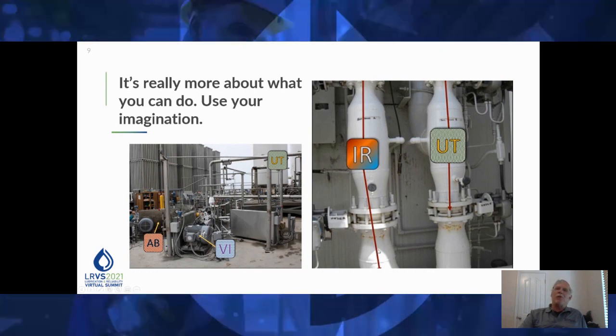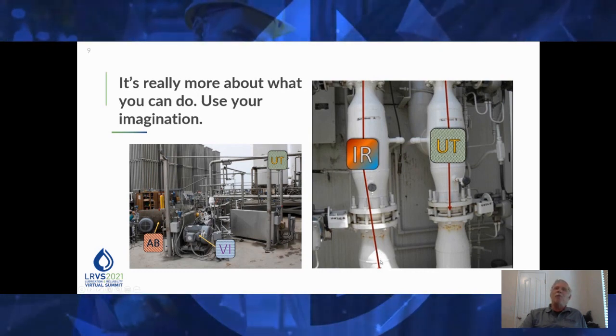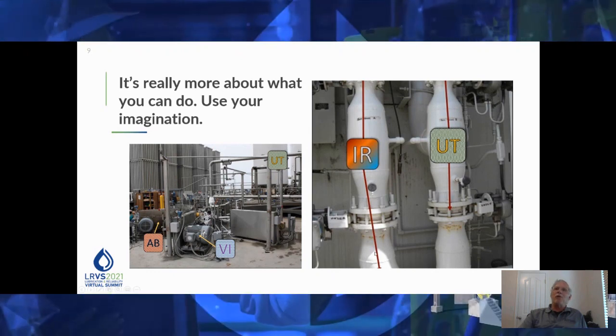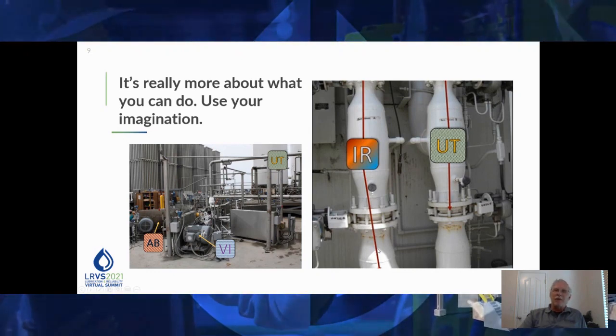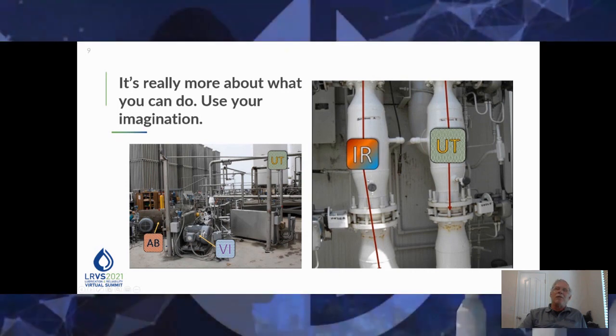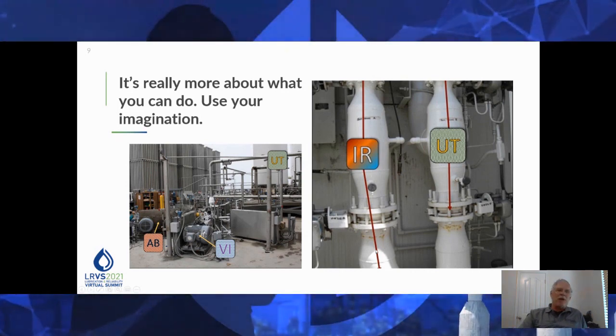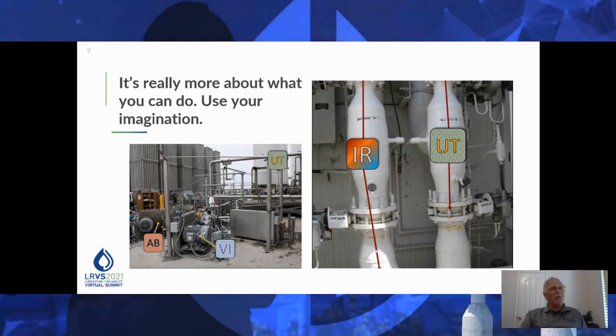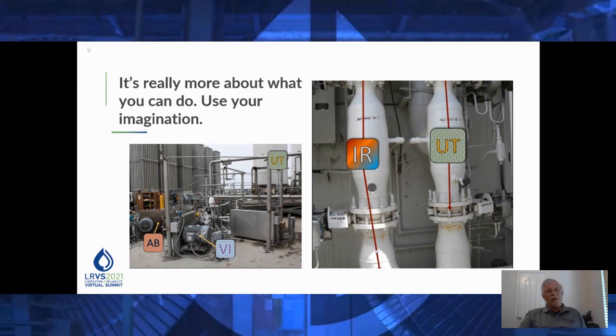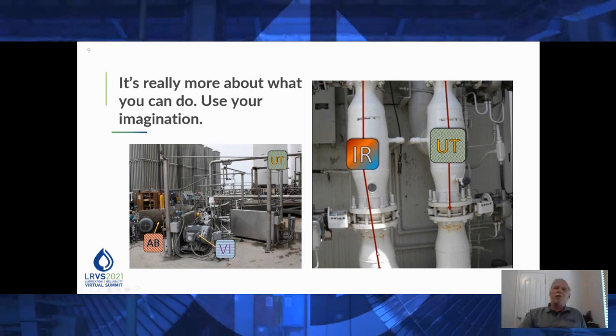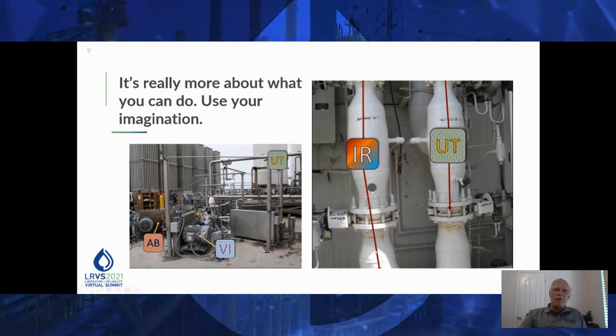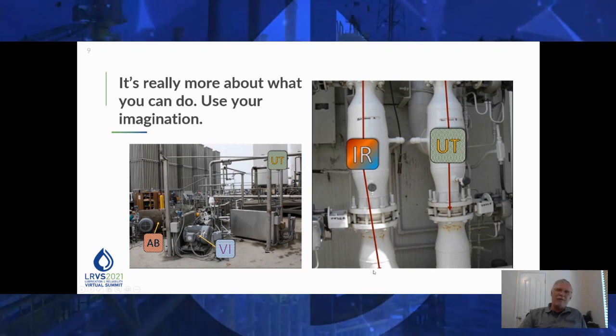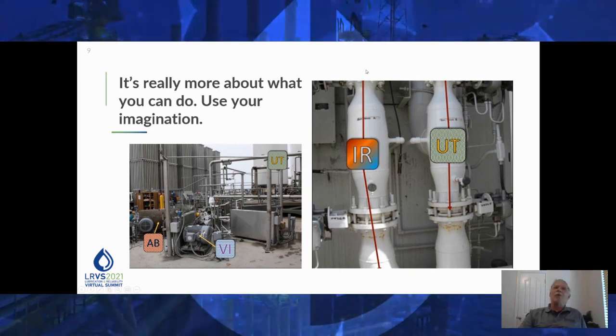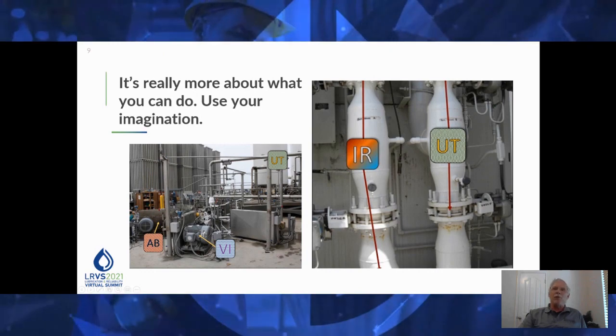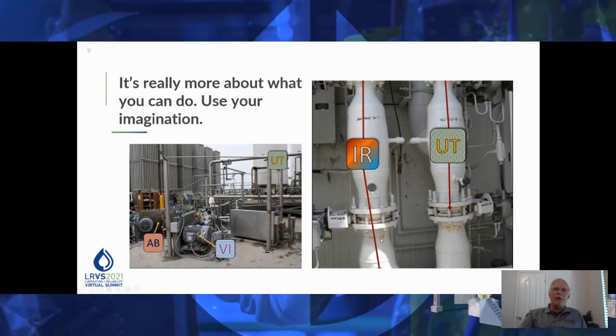As soon as we walked over there with the camera, we noticed a temperature difference between the top and the bottom. We had to sit back and think, well, is that supposed to be that way? In reality, no. There wasn't supposed to be any flow down the bottom. That was all supposed to be ambient temperature. All the flow was supposed to go up. Well, unfortunately, we had flow going both directions.